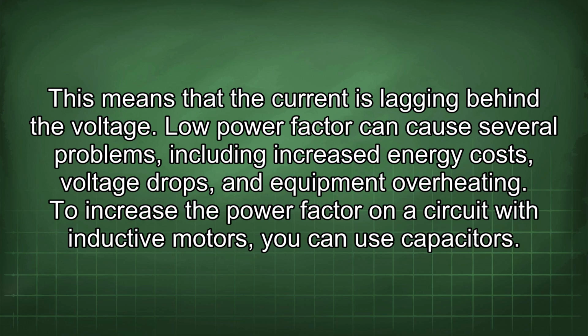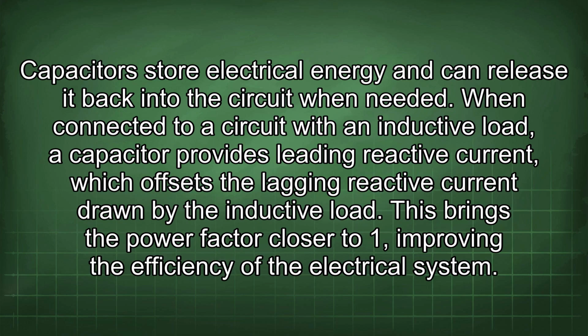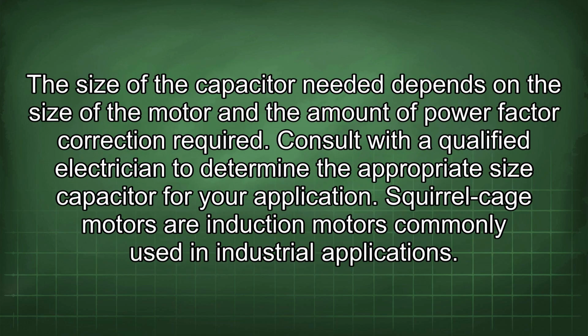To increase the power factor on a circuit with inductive motors, you can use capacitors. Capacitors store electrical energy and can release it back into the circuit when needed. When connected to a circuit with an inductive load, a capacitor provides leading reactive current, which offsets the lagging reactive current drawn by the inductive load. This brings the power factor closer to 1, improving the efficiency of the electrical system. The size of the capacitor needed depends on the size of the motor and the amount of power factor correction required. Consult with a qualified electrician to determine the appropriate size capacitor for your application.